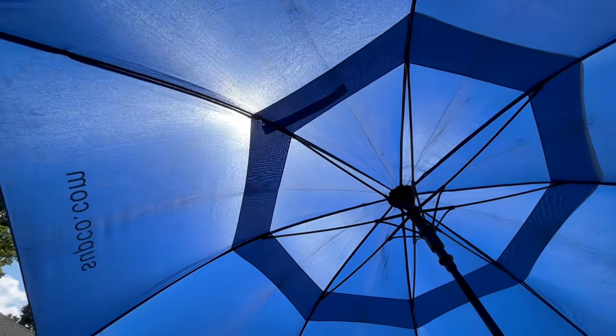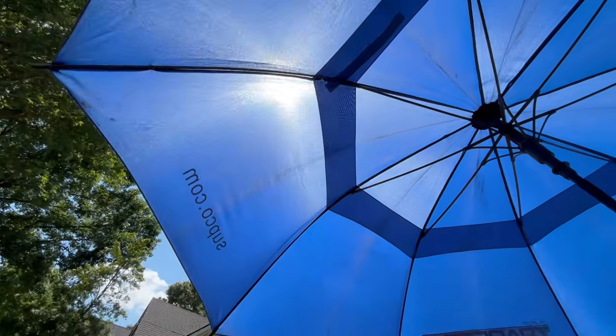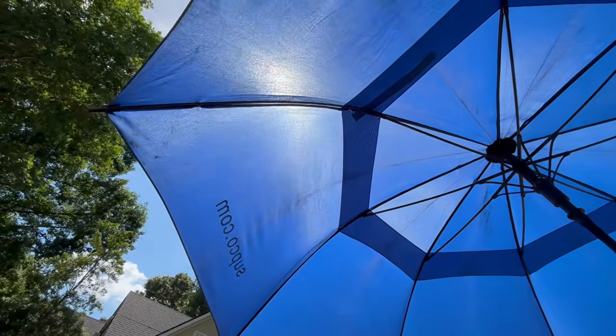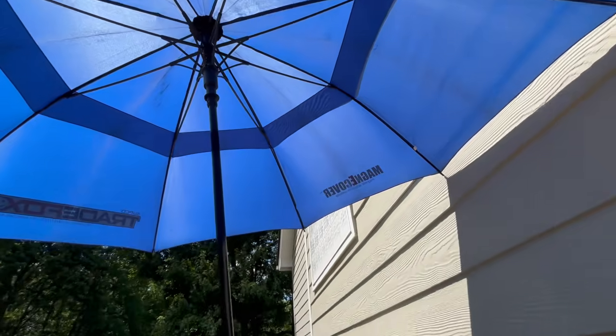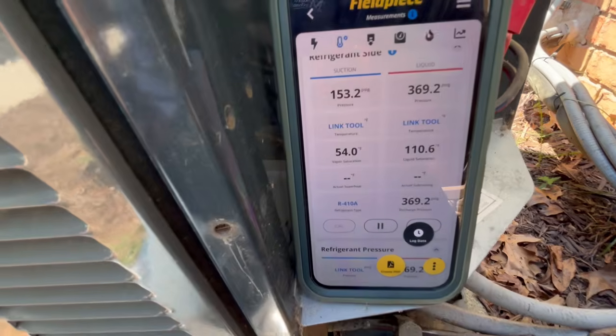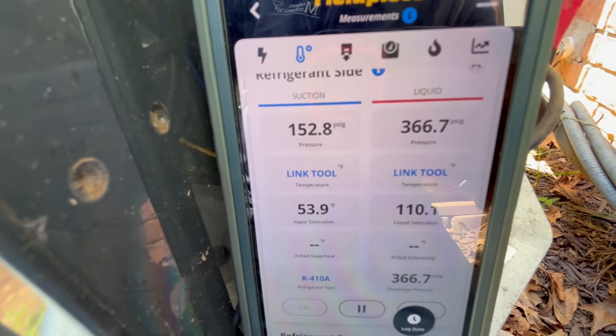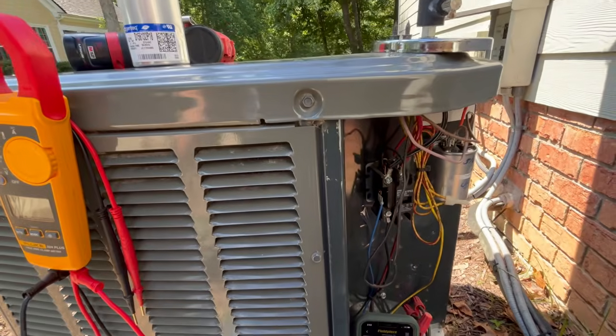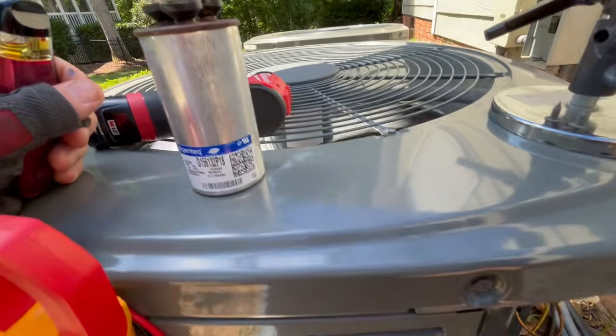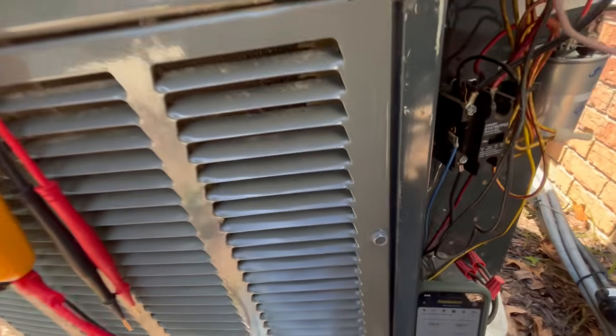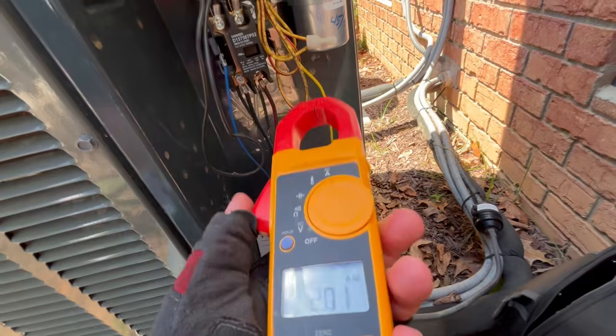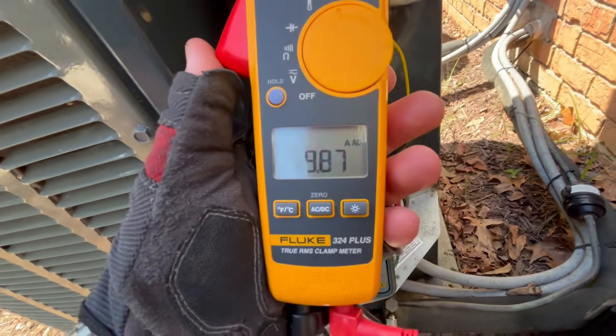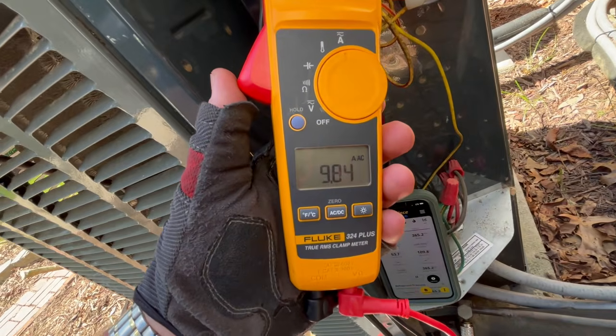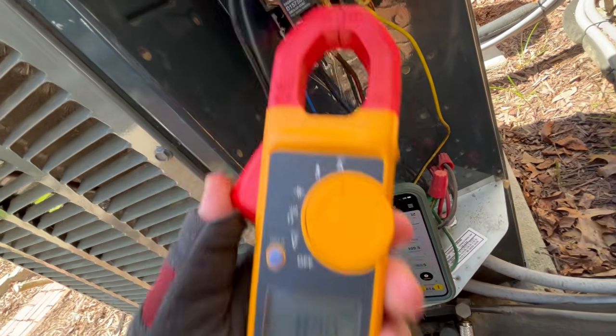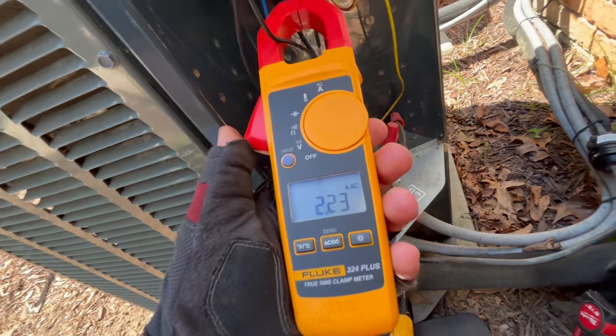These umbrellas come in handy when the sun's beating down. I have one, you might want to get one. Don't do much for the rain, but I have a bigger one for that. But anyway, pressures look good. We're at 152 and 367. It is 86 degrees upstairs, so there's a big heat load on that coil right now. And everything seems to be running fine. The compressor, we're at about 9.8, and it's running pretty hard right now. Fan motor, 0.67 on that.